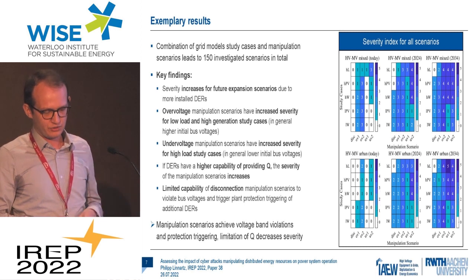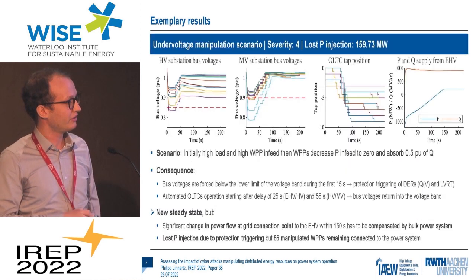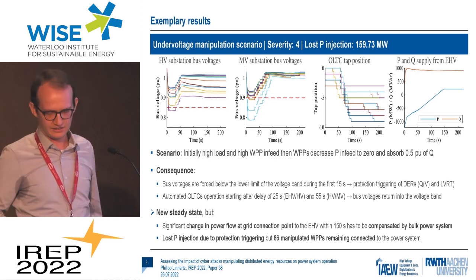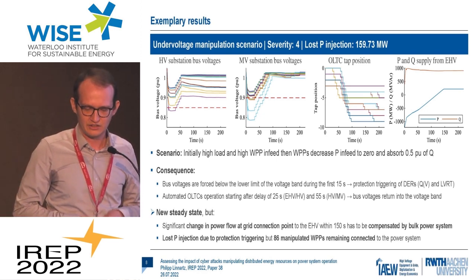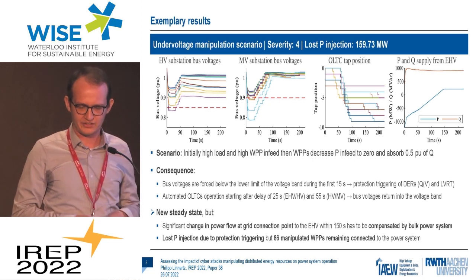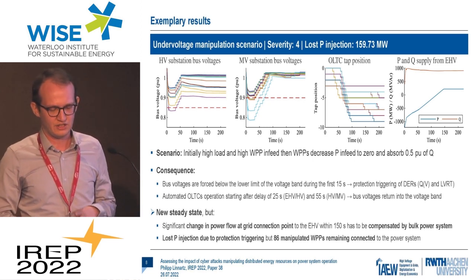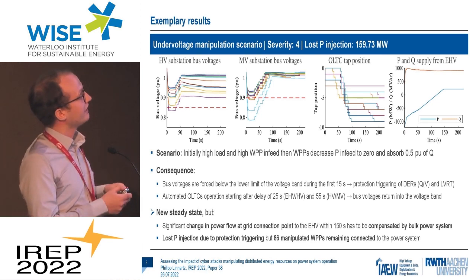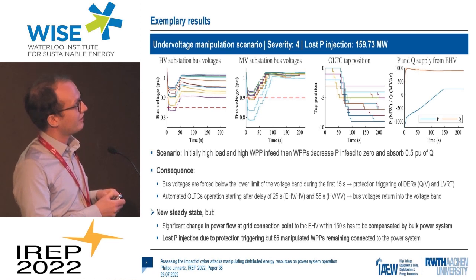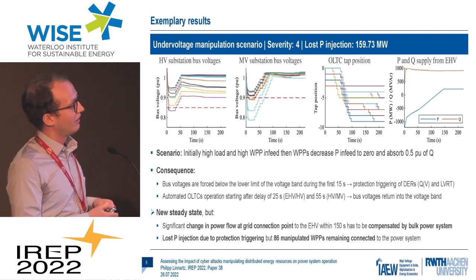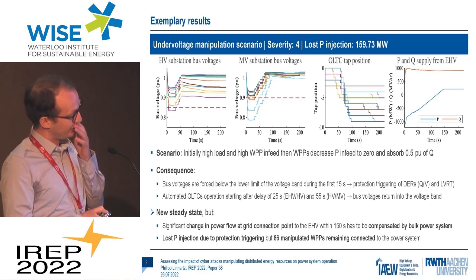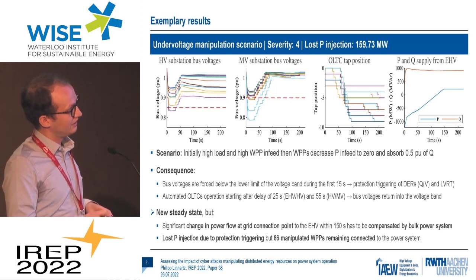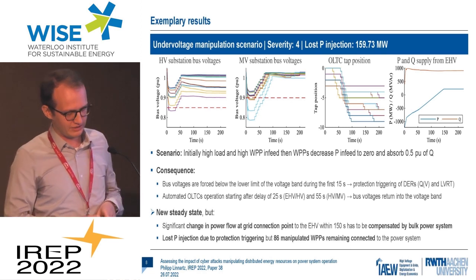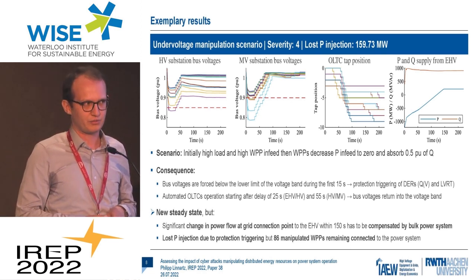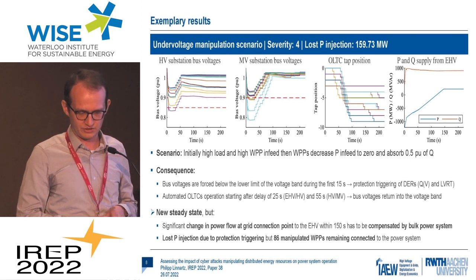I want to use the rest of my time to get into one of these scenarios in detail, so that you get an idea of what was actually simulated. I took one undervoltage manipulation scenario, which ended up with a severity of 4 and a lost active power injection of 160 megawatts. The 4 figures here indicate the bus voltages at the EHV-HV substations, at the MV substations, the OLTC, on-load tap changer, tap positions, why I will tell you later, and the power flow at the connection point to the bulk power system, or here the extra high voltage level.